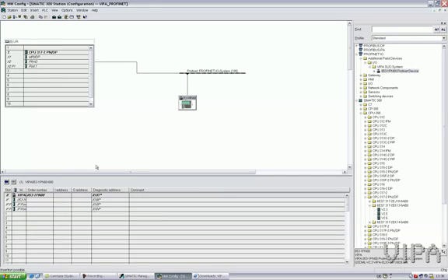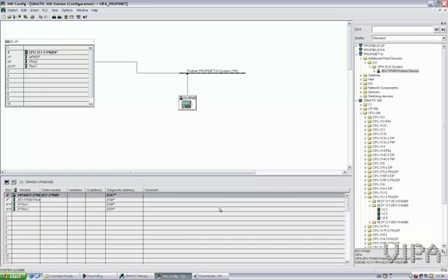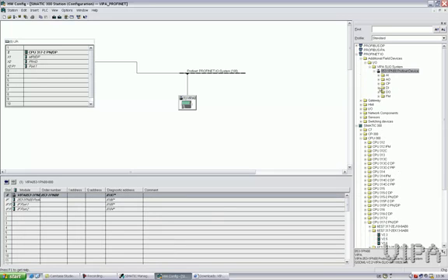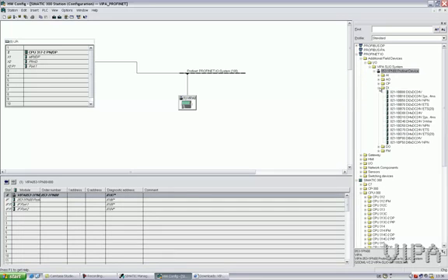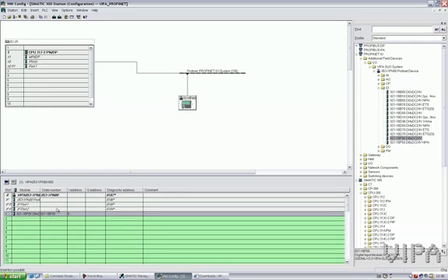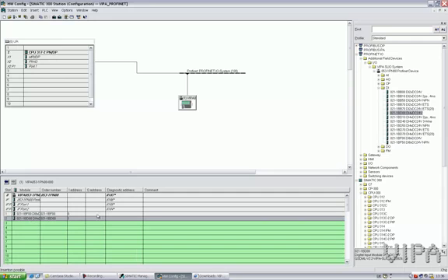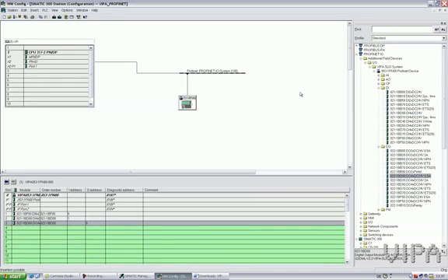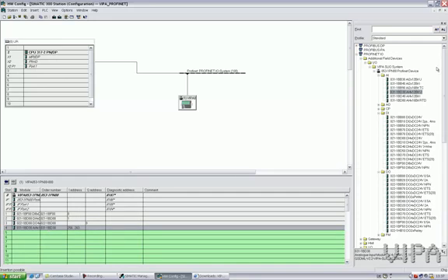Now, I can make the configuration of my IO system. I have a Digital Input module, the 1BF00. I have another Digital Input module, 1BD00. I have a Digital Output 1BD00. I have an Analog Input 1BB30, and I have an Analog Output, it's 1BB30 as well.